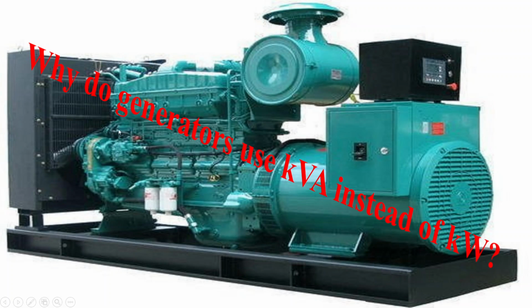Today we have a very interesting topic, that is, why do generators use kVA instead of kW? Generators are rated in kVA, that is the kilovolt ampere, instead of the kilowatt, because kVA measures apparent power, which accounts for both real power, that is the kilowatt, and the reactive power, kVAR.